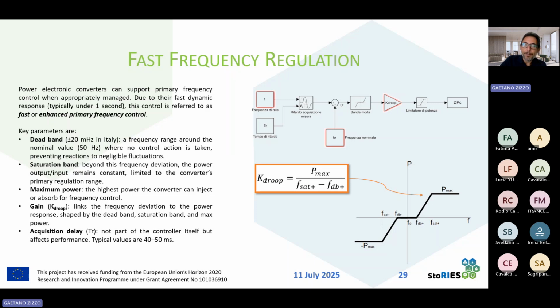We don't have a delay, because if compared to the intervention time of the turbine governors of classical power plants, the intervention time of a battery storage system is so small that usually it is neglected in this kind of representation. We are talking of a few hundreds of milliseconds, at maximum 1 second. So we can have the same regulating action of a thermal power plant, of a hydropower plant participating in frequency regulation, with a very high response time. For this reason, we talk of fast frequency regulation when we use storage systems for providing such a service.